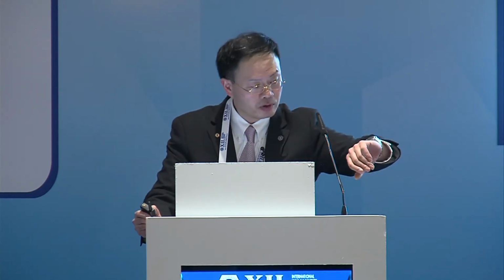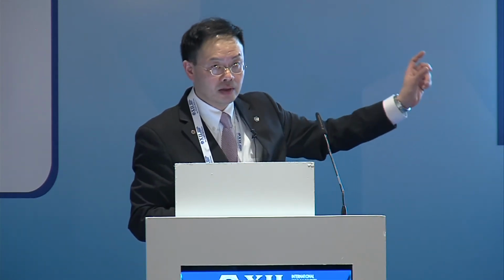The treatment of this offset flow defines the control strategy. In the US, typically we have three types: direct pressure differential control, differential flow tracking, and a hybrid control. Since I only have maybe 15 more minutes, I'll try to go very quickly. Pressure differential control: in this case, you may have an exhaust device like a fume hood or biosafety cabinet, and you control the room pressure directly and let the controller determine what the offset flow should be in order to achieve the delta P you would like.